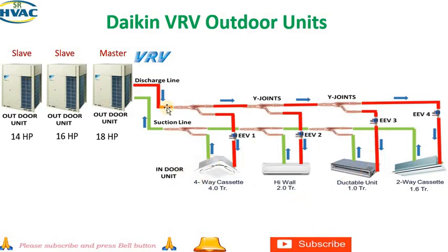If all the systems are running, meaning all the indoor units are working, then all three will work. If it is not required, the 14 or 16 will not work. It will work at 18 HP, and if it goes beyond 18 HP the others will start working. This way it is done. I hope you are now clear about master and slave in the Daikin VRV outdoor units.